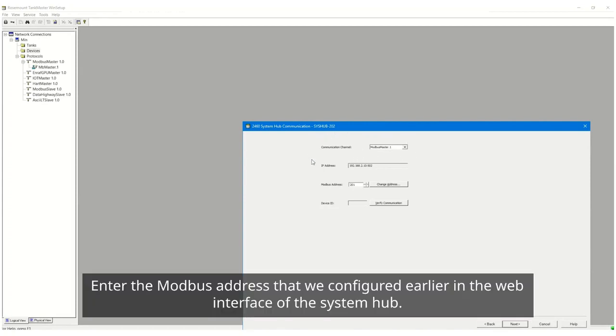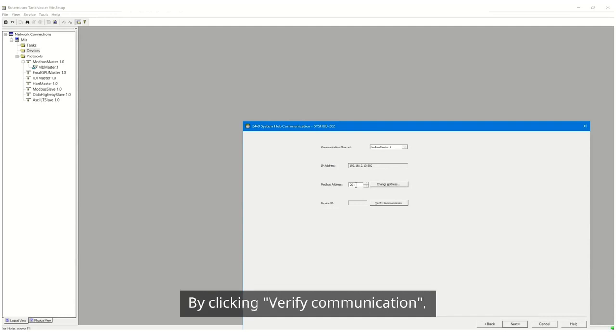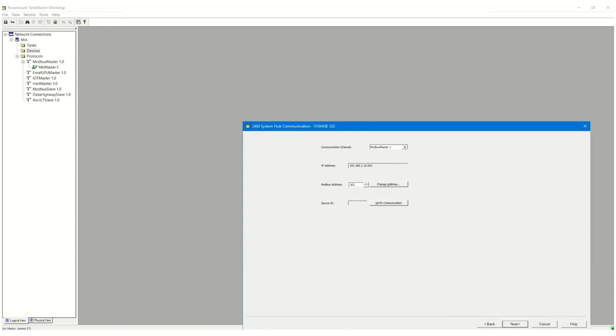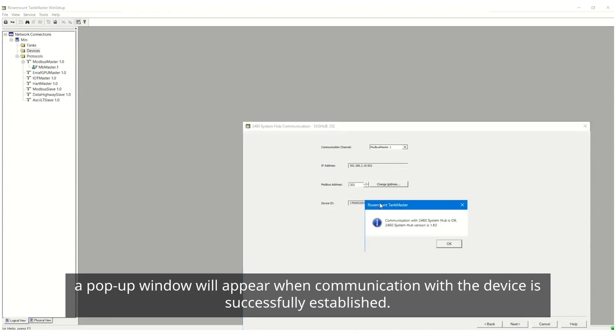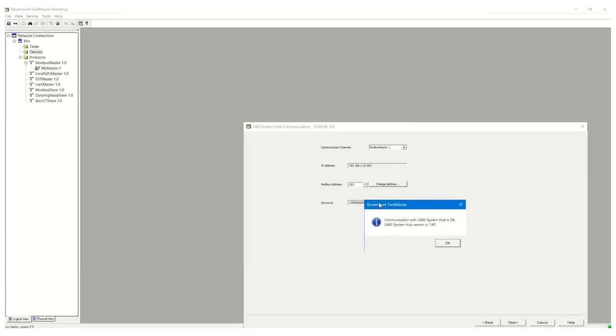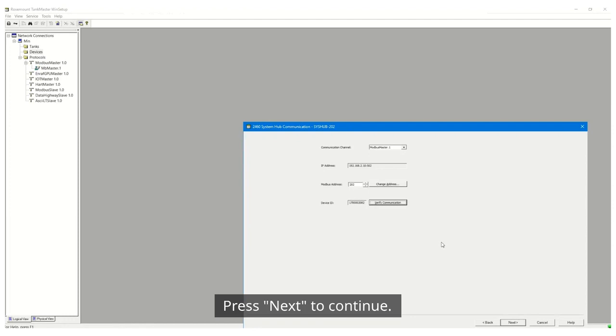Enter the Modbus address that we configured earlier in the web interface of the System Hub. By clicking Verify Communication, a pop-up window will appear when communication with the device is successfully established. Press Next to continue.